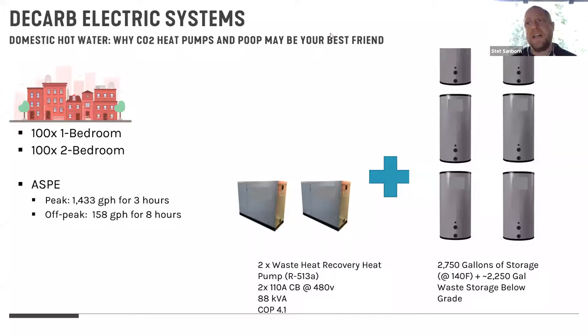Because I will tell you, the biggest limitation for electrification decarb work in a retrofit is my switchgear, is my transformer. It's what they built that building with in 1964. It's not code compliant anymore. So if I touch it, I have to fix it. So my goal is not to touch it. If it's safe to use, my goal is not to increase my connected load.